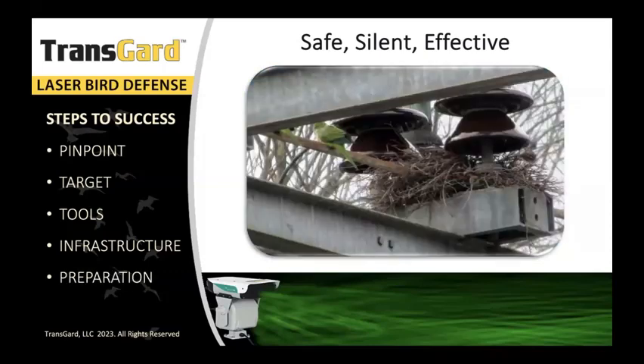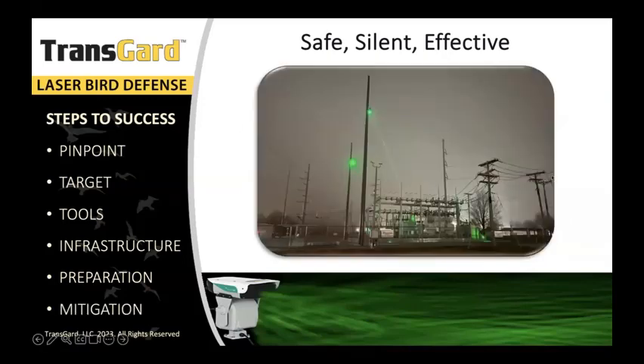So we look to prep, which is a thorough cleaning, and that means nest removal, guano removal, and cleaning of the equipment. And finally, we do the mitigation, which is installing the equipment and programming it. Once the equipment's up and running, it's pretty autonomous. It doesn't really need to be activated or looked at too closely, other than turning it off when you go into the substation and turning it back on when you leave the substation. We truly advise that it should be turned off when people are working in the sub itself.